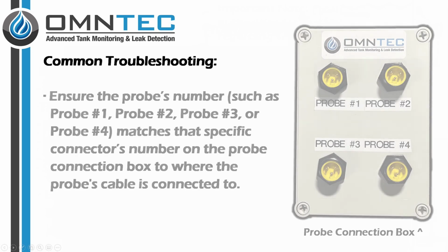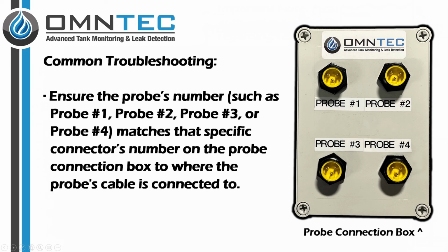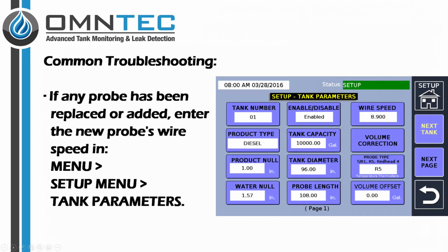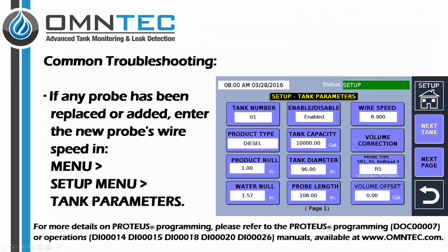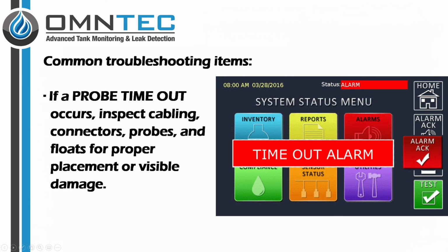The following are some common troubleshooting items should the test fail. Ensure that the probe's number, such as probe 1, probe 2, probe 3, or probe 4, matches that specific connector's number on the probe connection box to where the probe's cable is connected. If any probe has been replaced or added, enter the new probe's wire speed in menu, then setup menu, and then tank parameters. For more details on Proteus programming, please refer to the Proteus programming or operations manuals, available at www.omntec.com. If probe timeouts occur, inspect the cabling, connectors, probes, and floats for proper placement or visible damage.